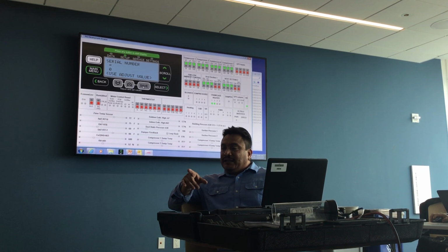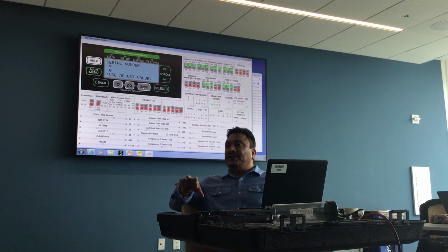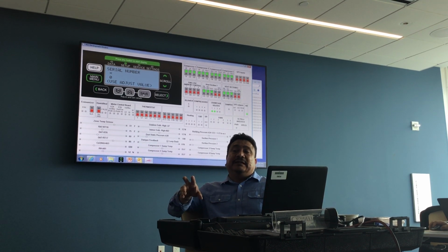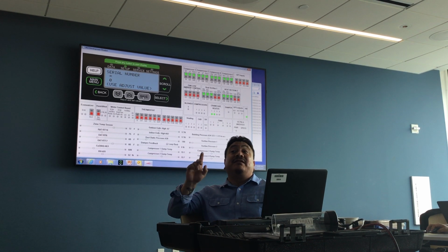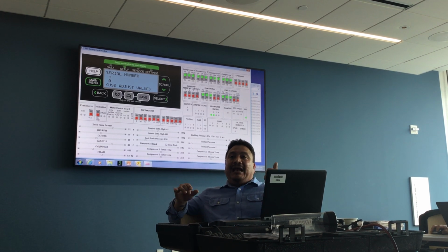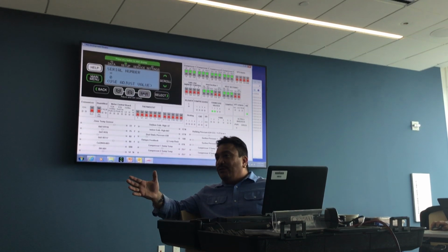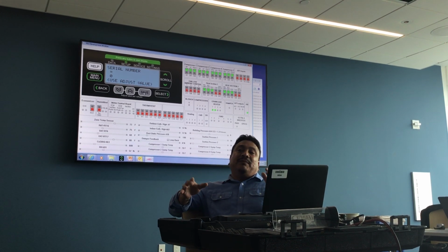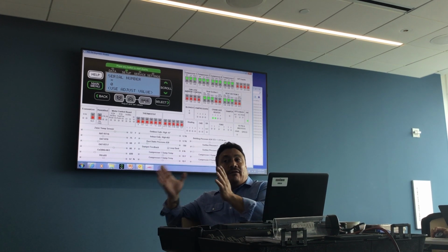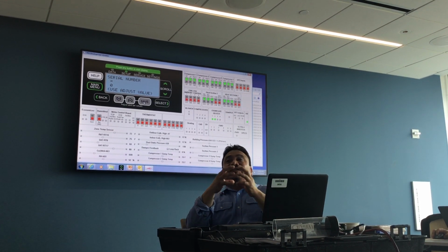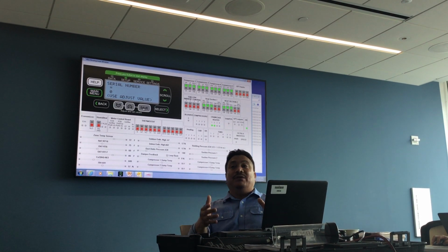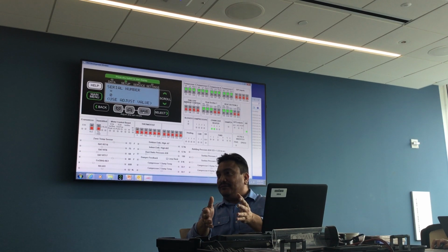Yeah. The serial number, like what he is mentioning, if it's a commercial grade unit, it's gonna have a 56, which stands for Stuttgart. Then, followed by the year. Then the next character represents the month that the unit was made. Now, we use an alphabetic nomenclature, A for January, B for February, and obviously we only go so far. So we narrow it down to basically the month and the year that the unit was manufactured and where it was manufactured from. Once you go beyond those characters, it represents the sequence at which the unit was made. So if you see 0356, that was the 356th unit made under that month and year.